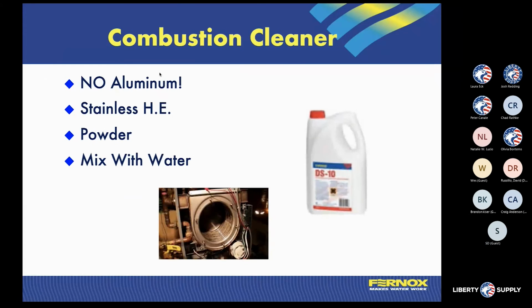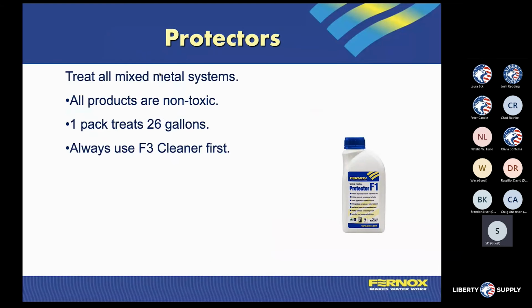For the heat exchanger side, we also have a cleaner. If you're cleaning out your heat exchangers, say you have a heat exchanger that needs to be removed and cleaned once a year, and you have it pretty built up inside, we have a product called DS10, which works similar to our DS40. You put it in a little spray bottle with some water, and it is a powder just like the DS40. That would also be able to break apart your carbon and any of the buildup that would happen in that heat exchanger. So this is talking about the combustion side or the burner side of the system as well.